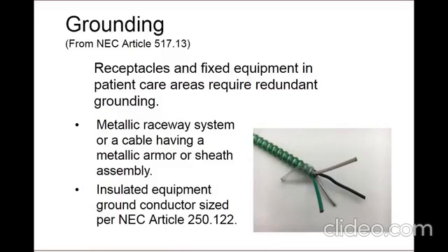All wiring in patient care spaces that serve receptacles and fixed electrical equipment must have 2 ground paths. The first required pathway is via the metallic raceway system or a cable having a metallic armor or sheath. The raceway system or cable must be suitable as an equipment grounding conductor in accordance with NEC 250.118. The second required path is with an insulated equipment grounding conductor. The insulated equipment grounding conductor must be connected to the grounding terminal of all receptacles, metal boxes, enclosures containing receptacles, and all non-current carrying conductive surfaces of fixed equipment likely to become energized.